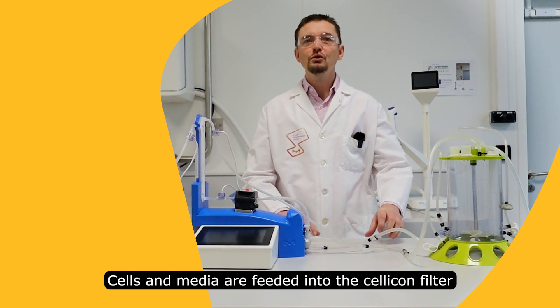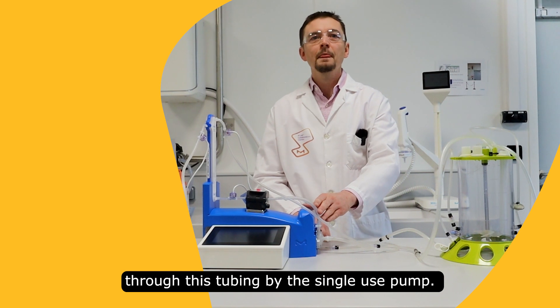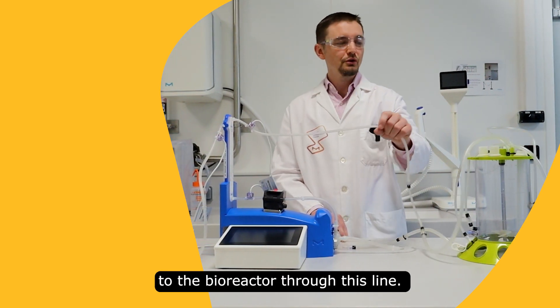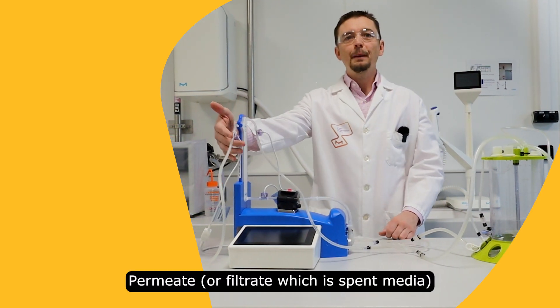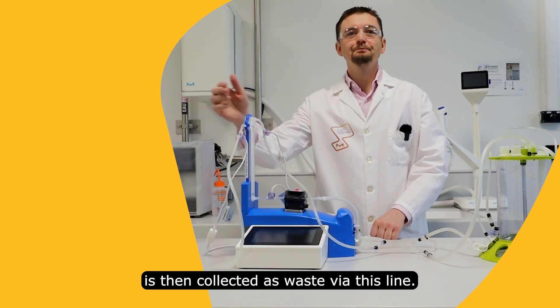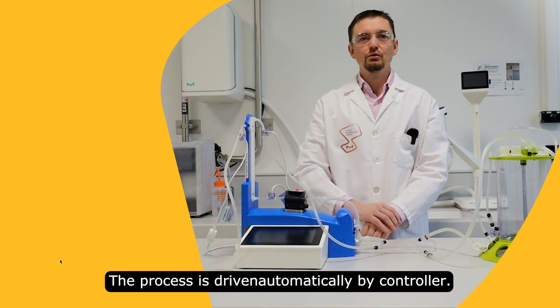Cells and media are fed into the Cellicon filter through this tubing by the single-use pump. Then the cells are retained and returned to the bioreactor through this line. The permeate or filtrate is then collected as waste via this line. The process is driven automatically by the controller.